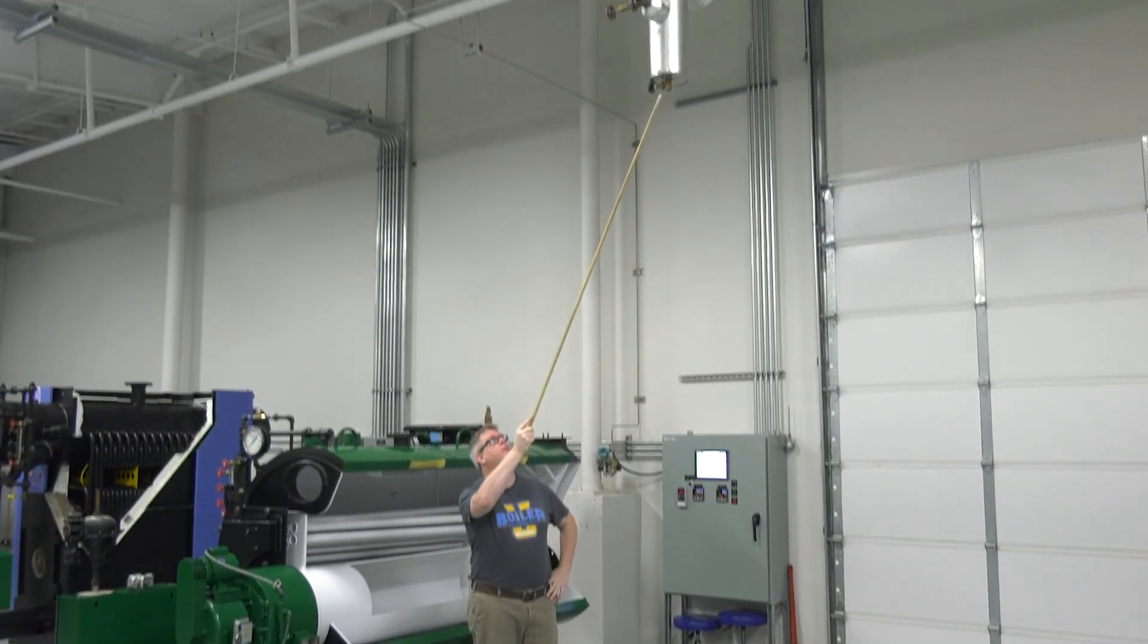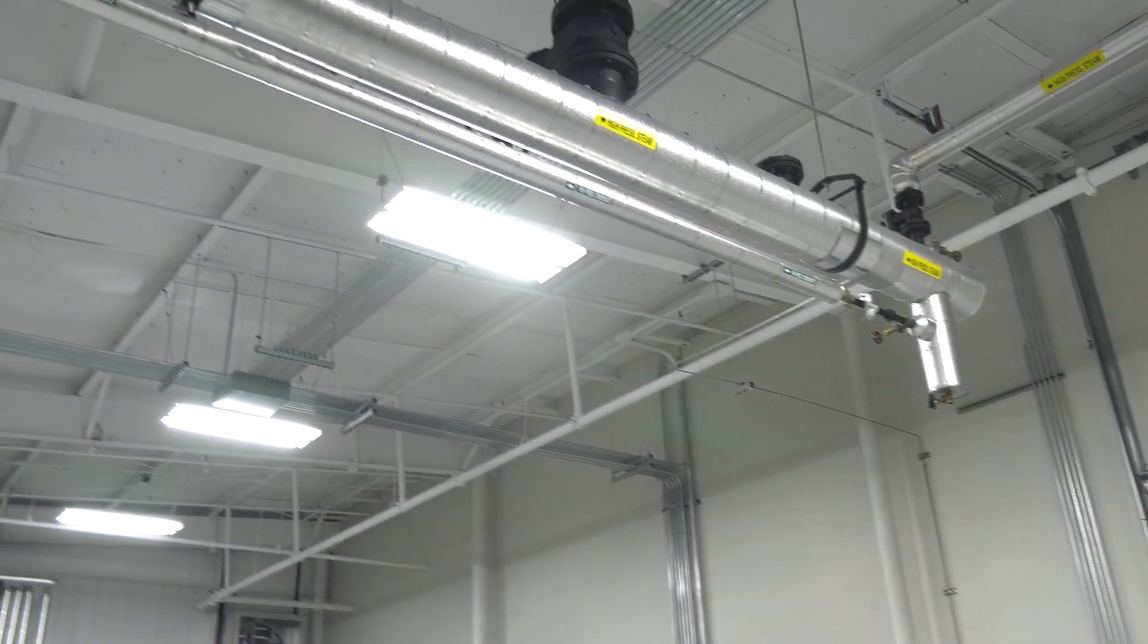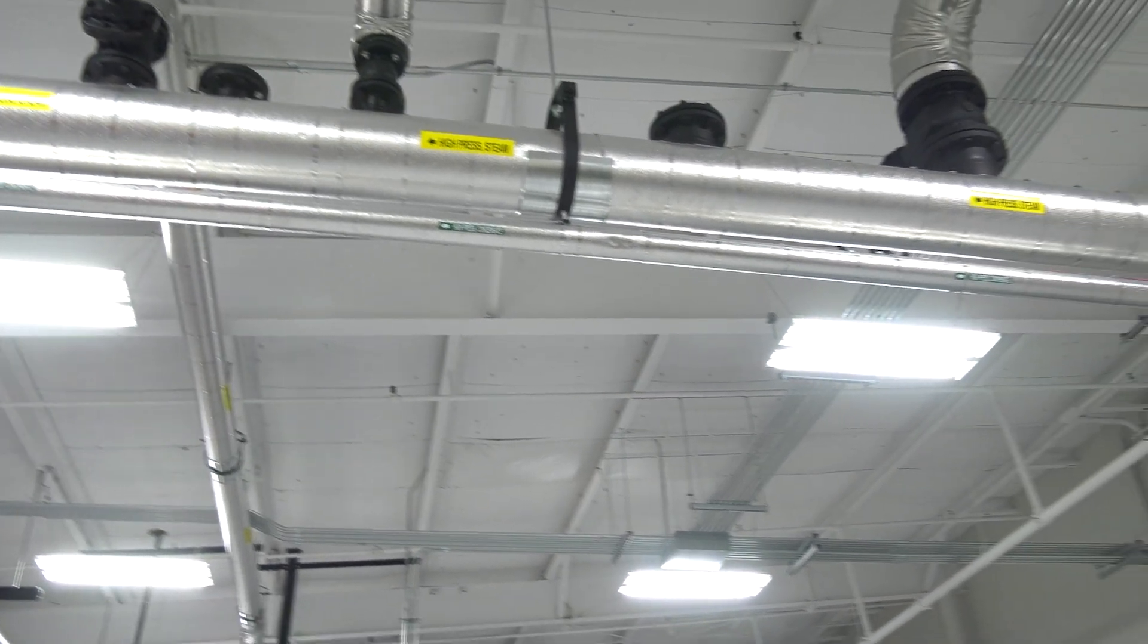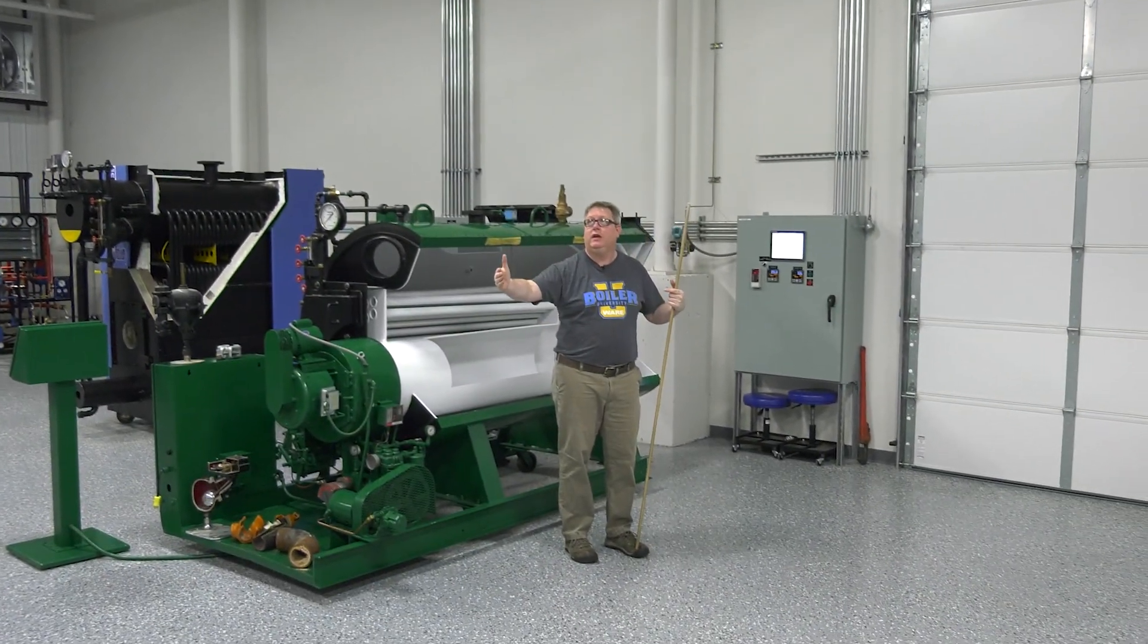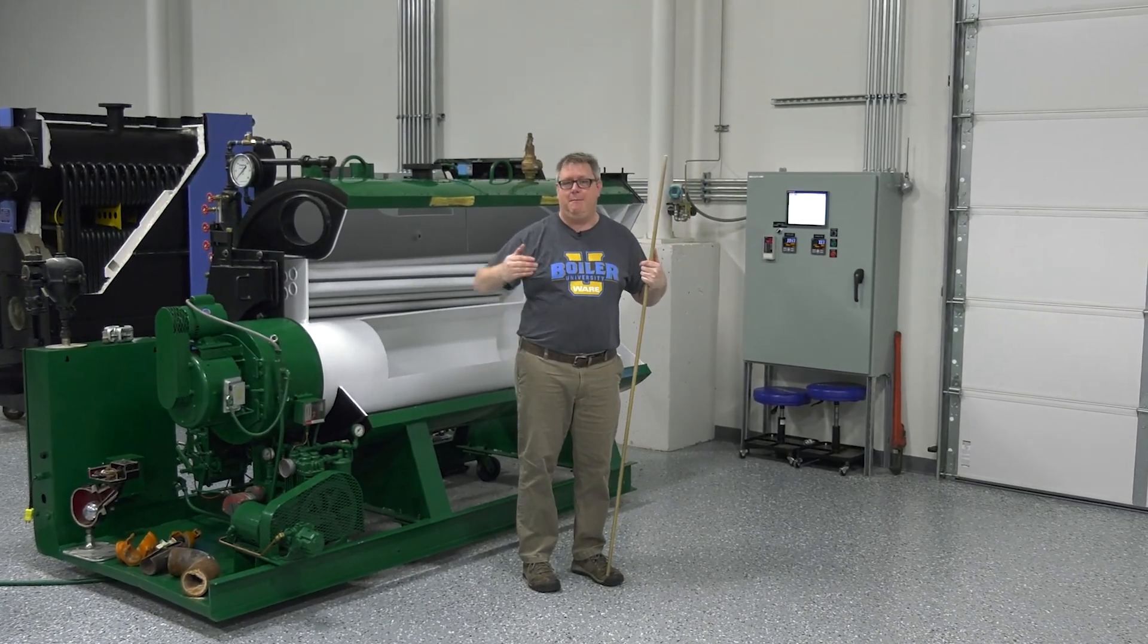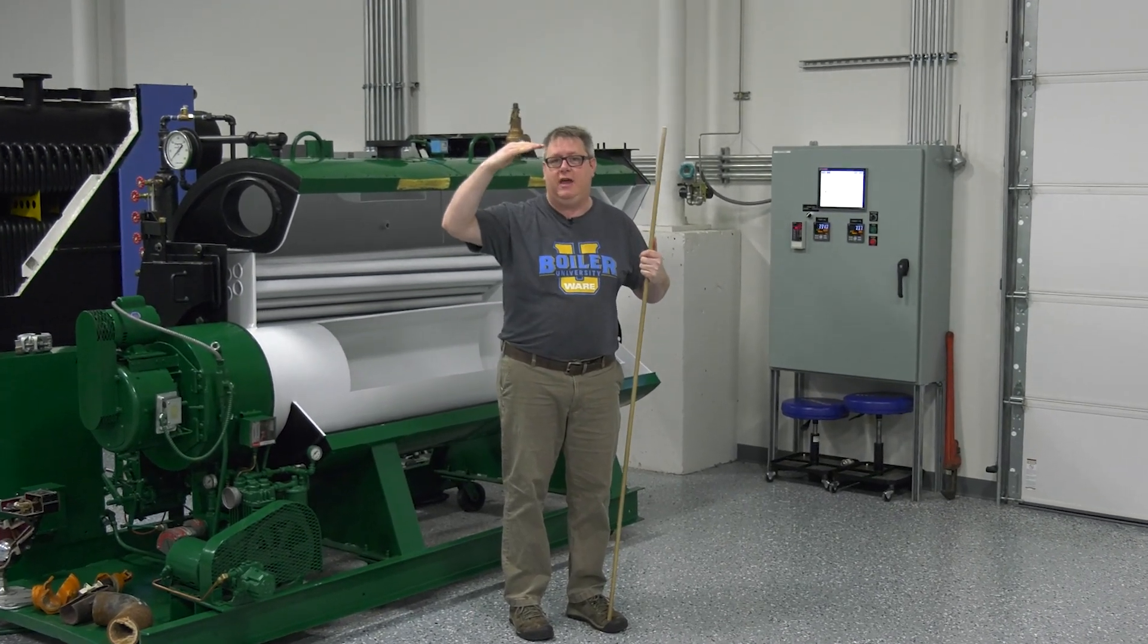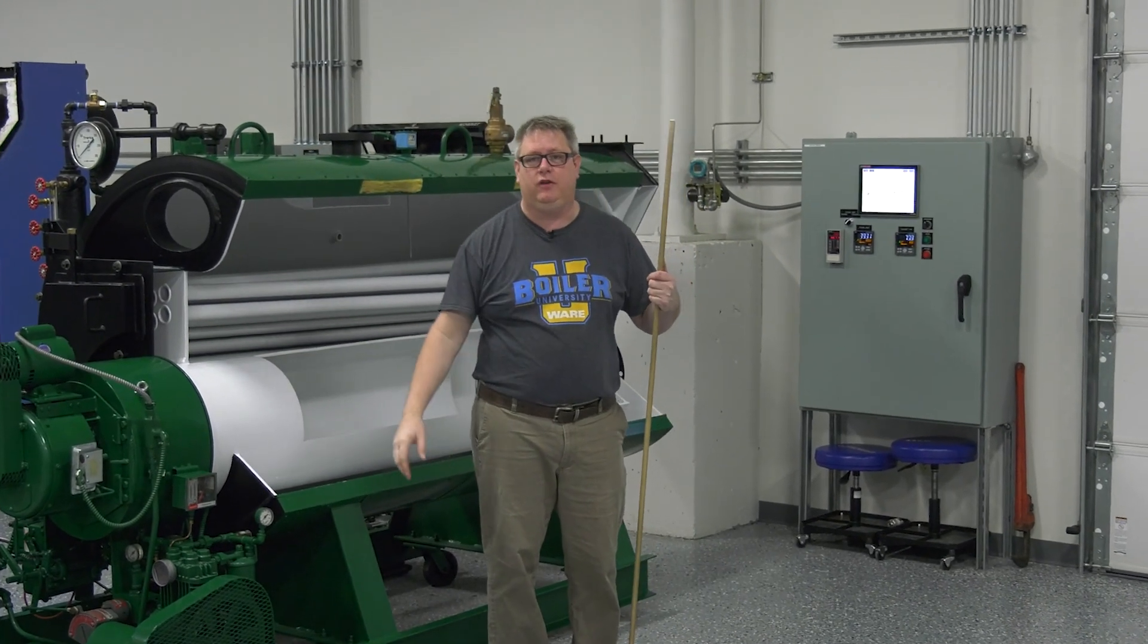Let's look at a couple other places where we've got drip legs on this system. In our steam distribution system, we're going to have a drip leg anywhere that condensate could accumulate. Basically on a header, we're going to have a drip leg on each end because the steam could travel in either direction. Without those drip legs, that header will flood with condensate until we start sucking condensate out in the pipe going to our points of use.